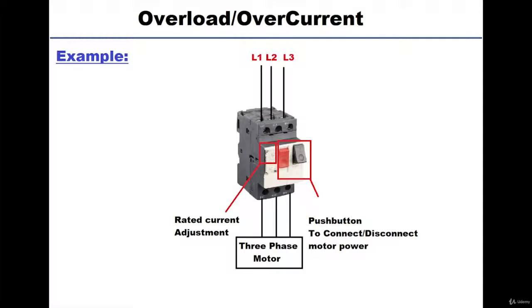So if you adjust your rated current to 10 amps and 11 amps passes through it, and this 11 amps lasts for 3 or 4 seconds, it will cut off the power and trip immediately. So they are more sensitive than circuit breakers.